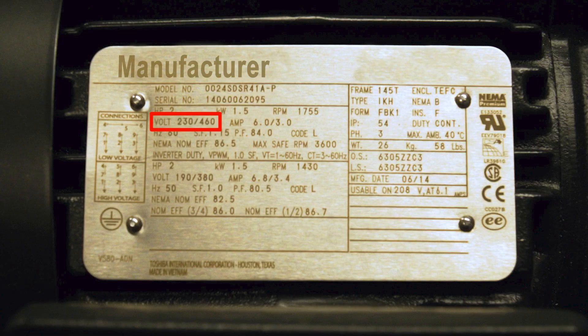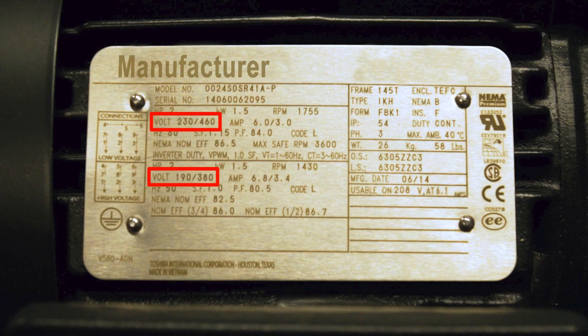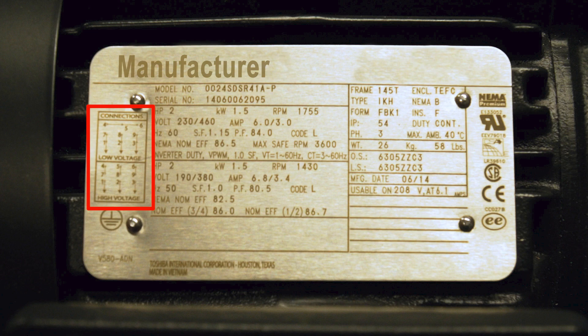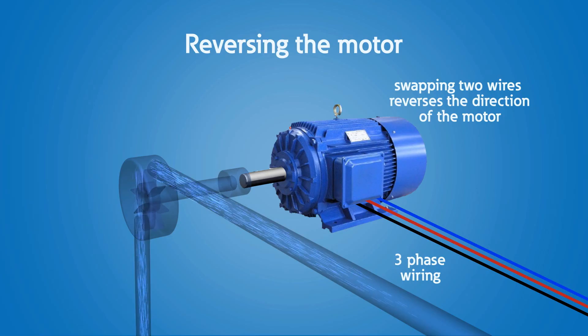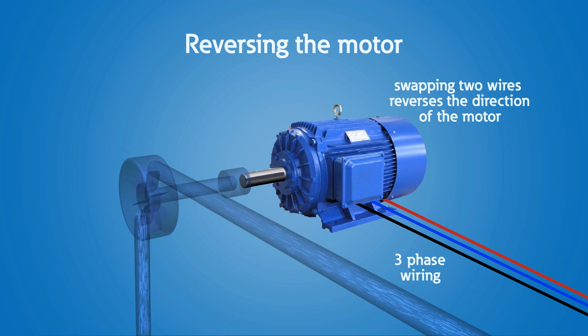And last but not least is the voltage rating. Standard NEMA ratings include 200, 230, and 460 volts. Motors can operate plus or minus 10% of this value. You might be wondering why the values aren't 240 and 480 volts like our power systems are rated — this is because the voltage rating of the motor accounts for voltage drop in the system and stator windings, so you would in fact use a 460 volt motor on a 480 volt system. Typically, multiple voltages are listed on the nameplate, and you'll see a wiring diagram that you need to follow carefully to connect the stator windings for the high or low voltage rating. You can also reverse the direction of a motor by swapping two of the three phases of the incoming power connection. If you get the phasing wrong, you will have a fan or pump spinning backwards during startup. This is why electricians will bump start a motor for the first energization to check its rotation.